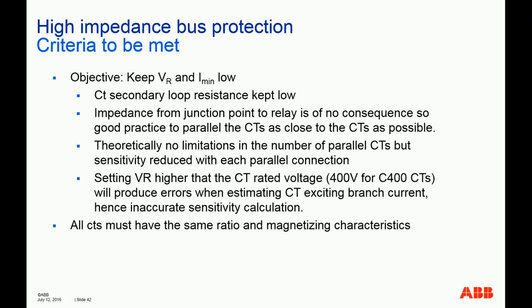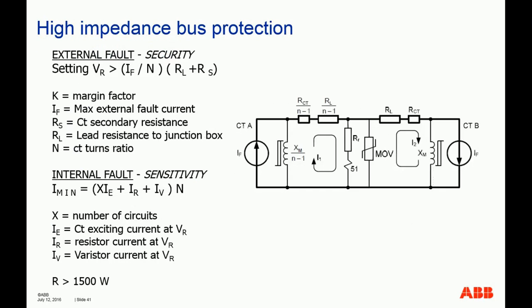So how to reduce it? Obviously, as I mentioned, reduce the RL. How to reduce it? You can try to keep the CT secondary loop resistance low. How to do that? Impedance from junction point to the relay, that is of no consequence. So what it's saying is, because of the huge resistance here, it doesn't matter how long this portion is, and this portion represents the junction point to the relay terminal.